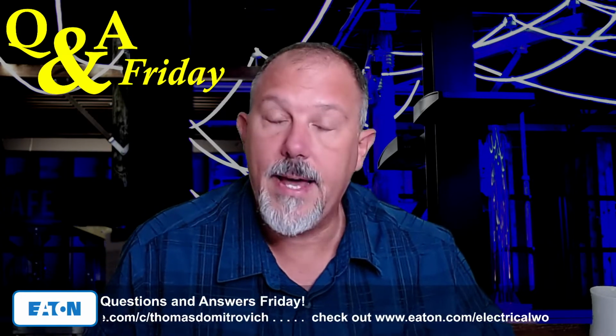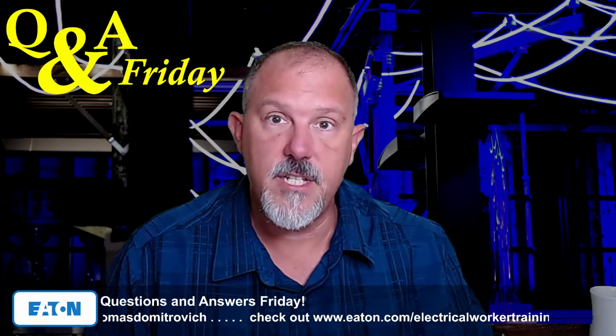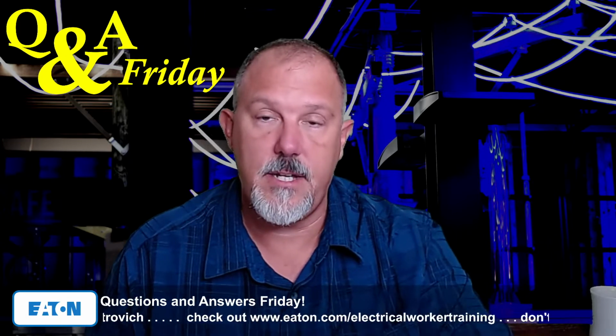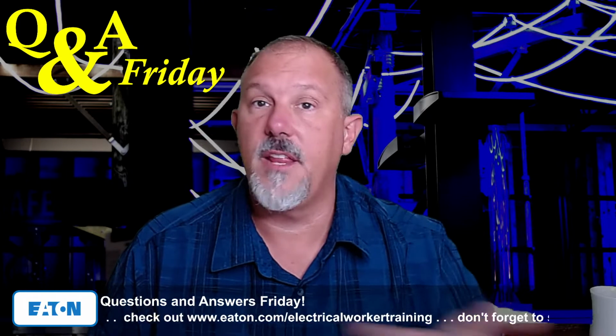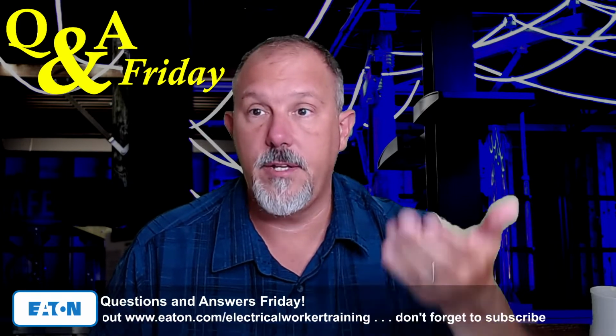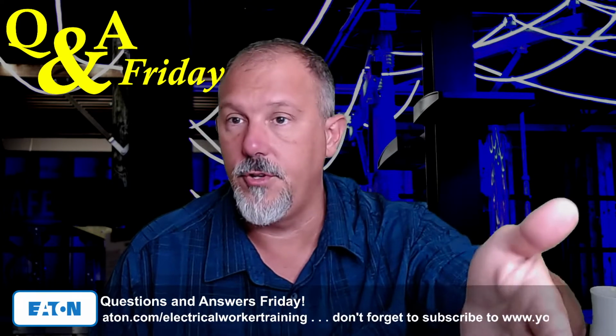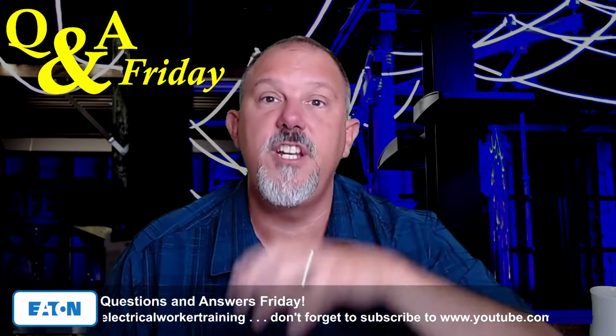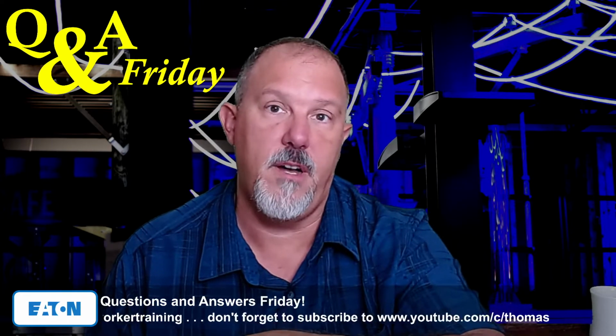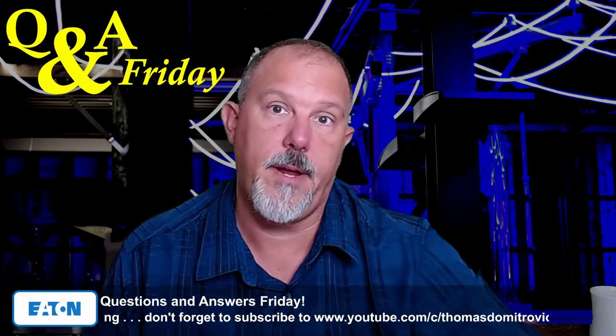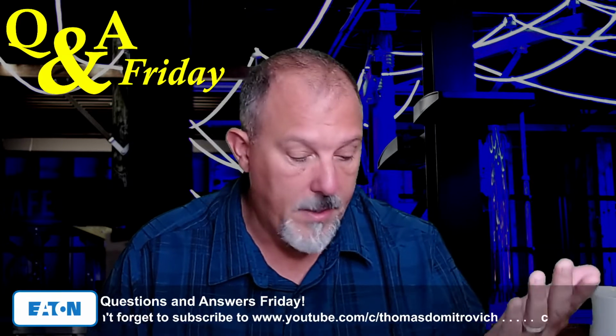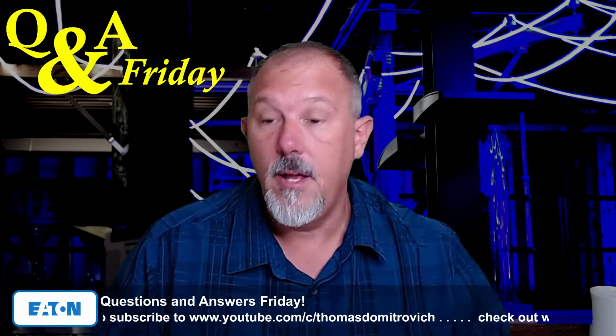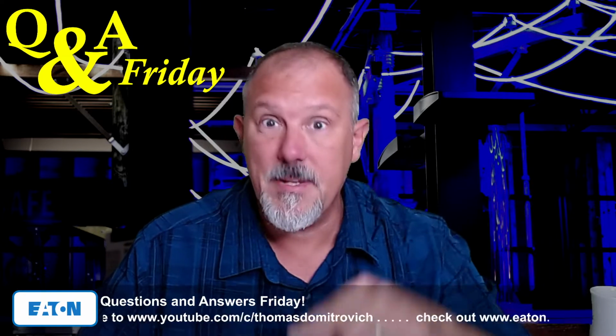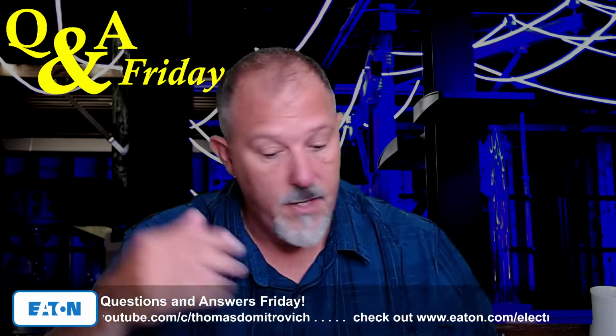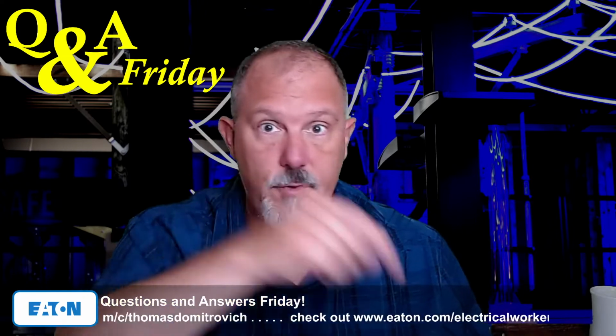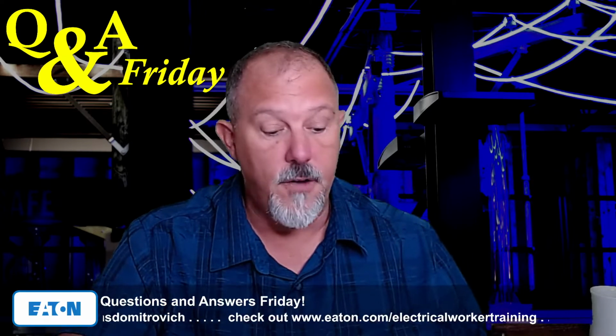So if you had a circuit breaker sized for the locked rotor and SCCR, do you not put GFPE at 1000 amps and above? So in New York, or not New York, in your jurisdiction, do you not put GFPE on a 1000 amp breaker and above because it's sized for locked rotor amps? That would be a question there. If you do the same thing there, then I think we need to talk. But the same exact language, which is in 230.95, we've got over here in 240.87. So whatever you do on 230.95, you better be doing for 240.87.